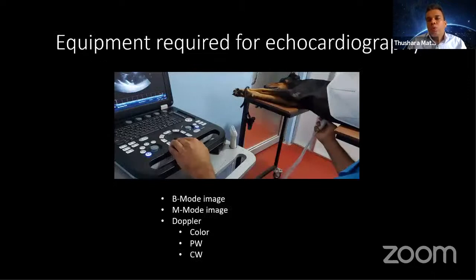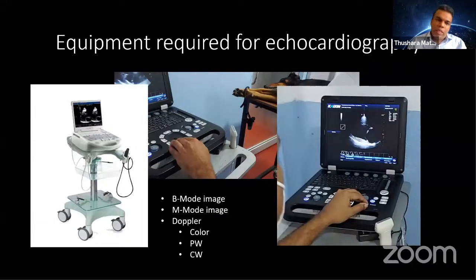To do echocardiography, we need a special machine. This machine should have some technical requirements. Usually this is the ultrasound machine we use in Sri Lanka. We can use this Esaote machine or some Chinese machine here. This machine should have B-mode imaging facility. All ultrasound machines have this B-mode imaging facility. It's a 2D image. We can get a black and white image of the patient. Then M-mode examination. I'll explain M-mode later. Then it should have color Doppler examination, and for Doppler we should have color Doppler, pulse wave Doppler, and continuous wave Doppler. To do complete echocardiography, we should have these facilities in the ultrasound machine.